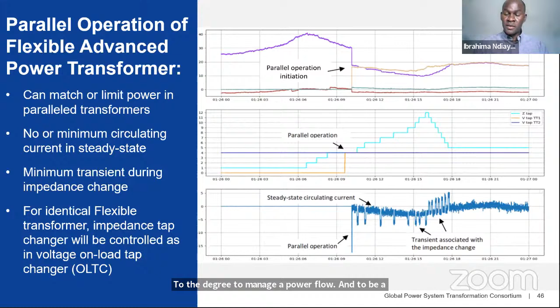There was no tripping, no voltage dip whatsoever. So this proves again that the flexible transformer can operate fairly safely on the grid to manage power flow and to relieve scenarios such as congestion, as many have talked about, or grid reconfiguration during contingency. And the next slide is my last, just to sum up. The design and development of a flexible power transformer can comply with existing standards. In North America, we apply mainly IEEE, and it can also be designed to comply with IEC standards.